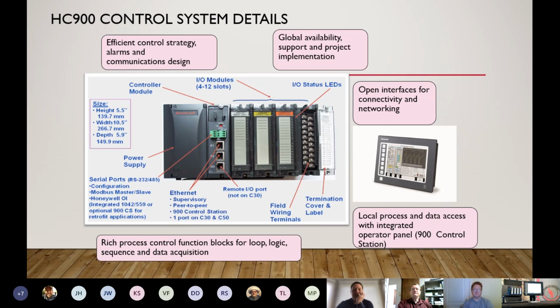So as we move through this product, I want you to think of it in that fashion. If you have an application with 3 or more control loops, UDC controls, this might be a good substitution for that, giving your customer, the plant, or the operators a little bit more visibility into the process with troubleshooting, diagnostics, alarms, screens with graphics, things of that nature.